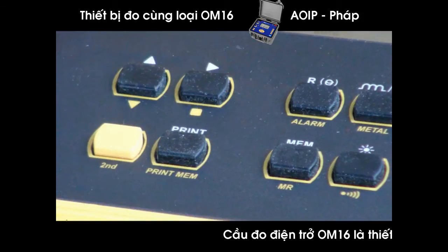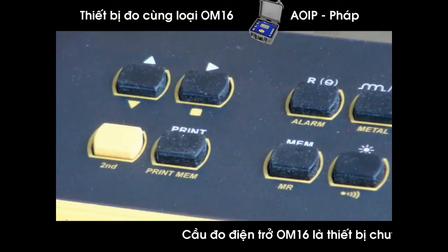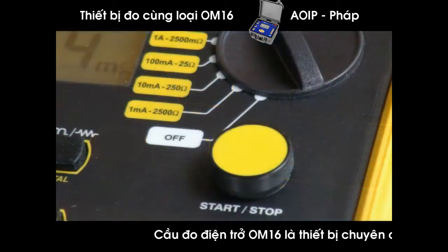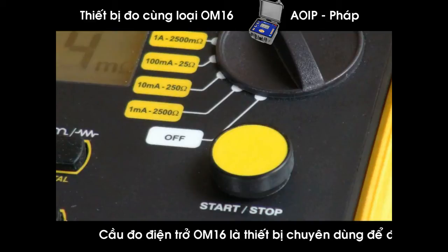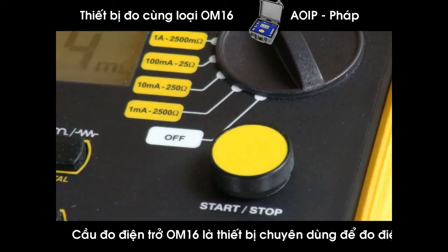We're going to stress this bonding connection where two particular pieces of metal are touching, be it welded, or a cinched-down or torqued-down lug and a bus bar, for example, in the case of power wiring.